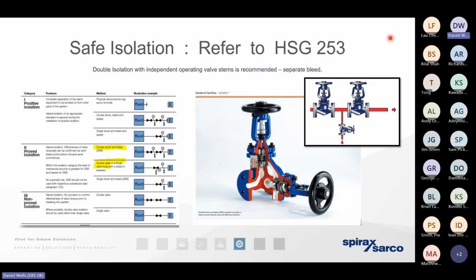they will refer to what we call double block and bleed or safe isolation standards. As you can see up in the little pop out at the top corner of the screen, this is actually 3 individual valves. So if there were a risk of that first metal to metal valve eroding, any steam that is passing across could obviously create a health and safety incident to anyone that may be thinking they're working on a process safely. So we install a second valve downstream, the idea being that we've got a second chance of stopping that leaking steam and preventing a health and safety incident.